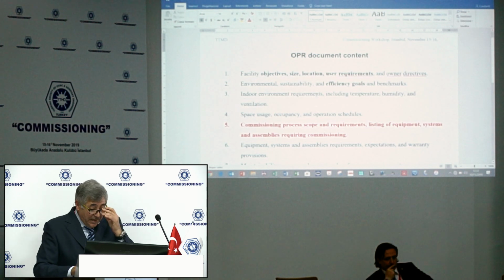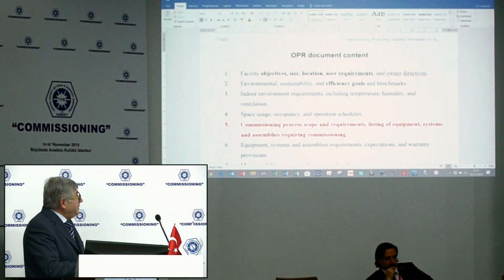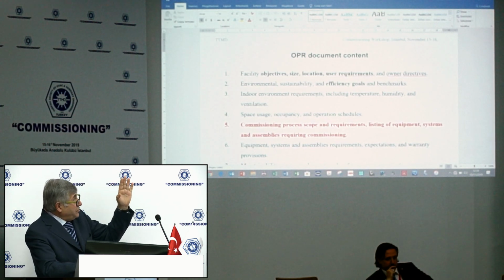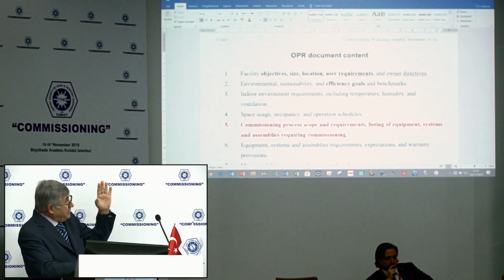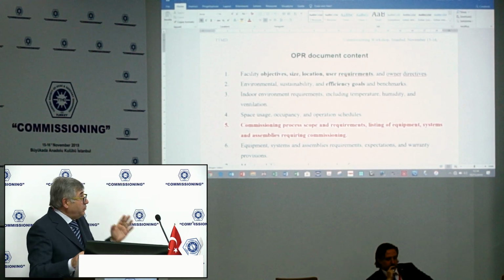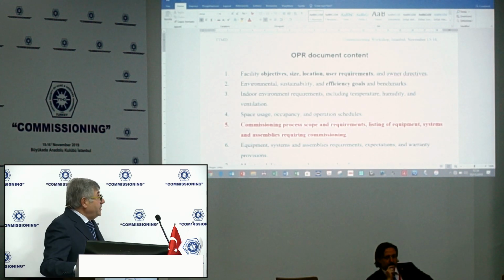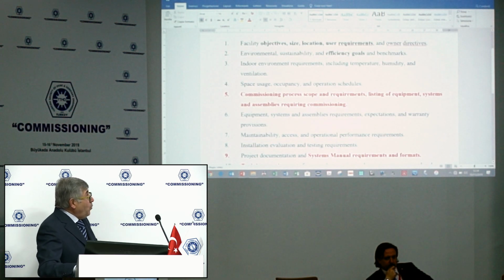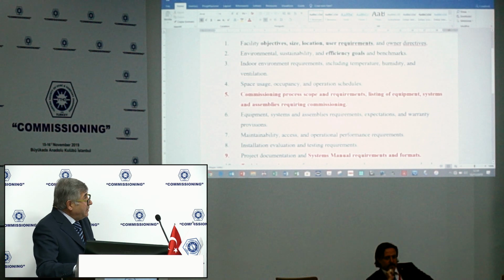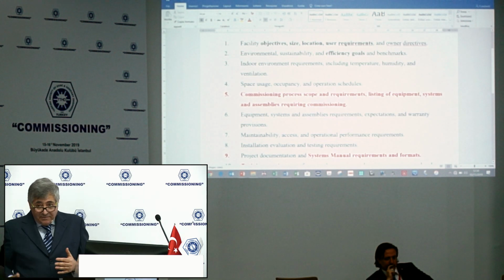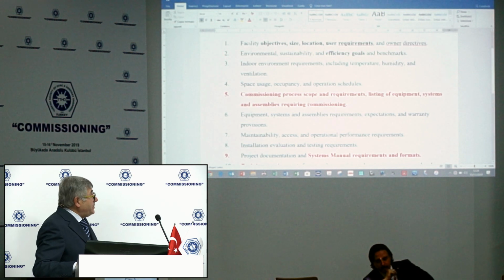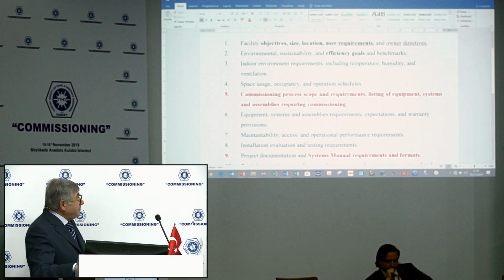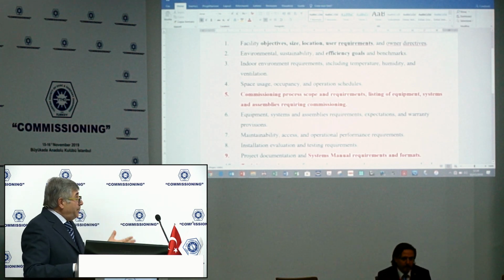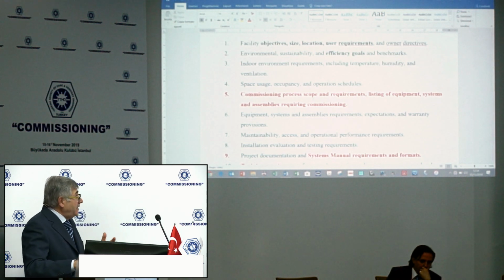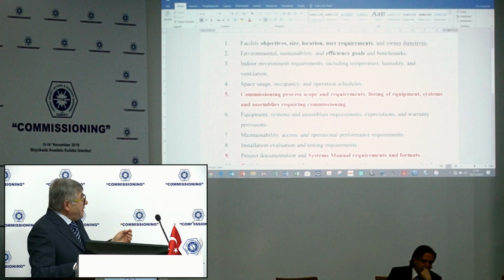The owner has to indicate the facility objective, size, location, user requirements, owner directives, environmental sustainability, efficiency goals, indoor environment requirements including temperature, humidity, ventilation, and so on - space usage, occupancy, operation schedules, commissioning process scope and requirements, and a list of equipment, systems and assemblies requiring commissioning - some pages listing which equipment needs to be commissioned, or which equipment the owner wants commissioned.